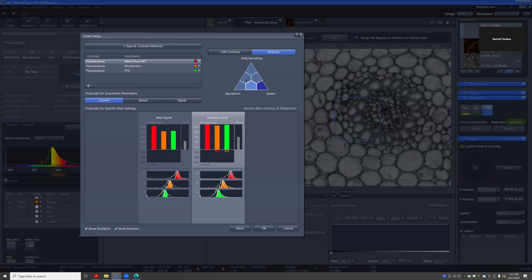The other ones in the middle are called multiplex 4Y, multiplex 8Y. Those numbers just stand for the amount of pixels that it grabs simultaneously. So of course, 8Y would be quicker than 4Y. Then there's something called confocal 8Y. That's the quickest mode. That's the fastest scan mode on the Airyscan. As a starting point, I'd say that's good to start out with.